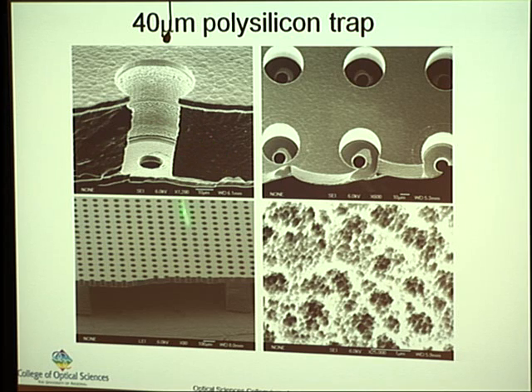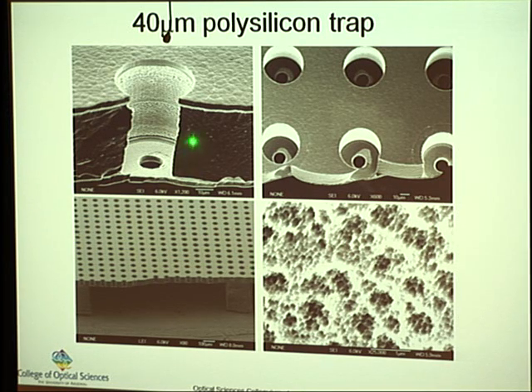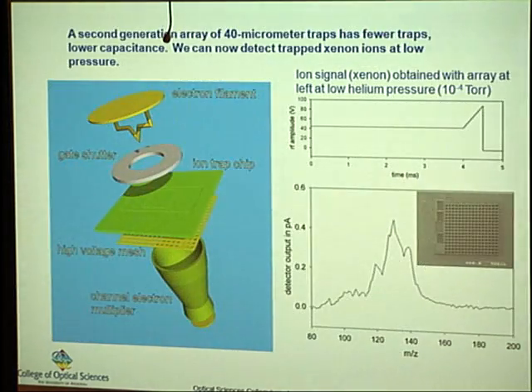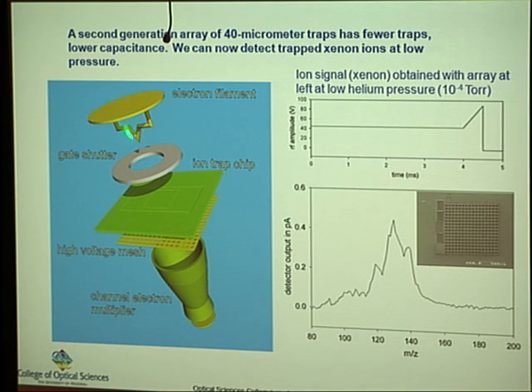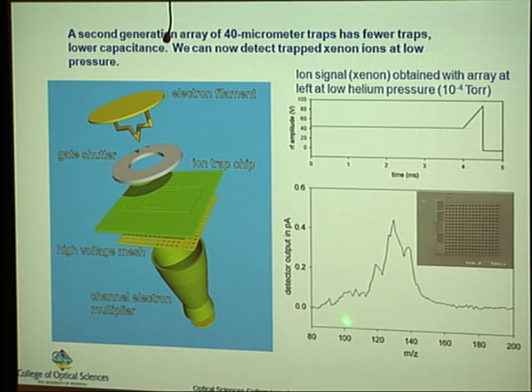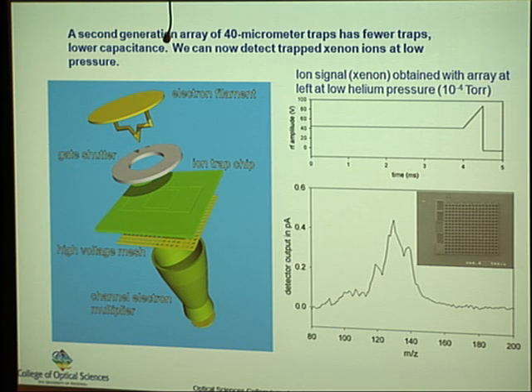We have not just one ion trap but an array of them, microfabricated at Bell Lab, consisting of three electrodes: a top ring, middle ring, and bottom ring electrode. We actually got this to work. The setup uses the chip with an ionization source — field emitters — and a detector, a channeltron. This is one of our first results demonstrating pretty low-resolution mass spec, but it was the first time anybody had done mass spectrometry using a microfabricated trap of this dimension.